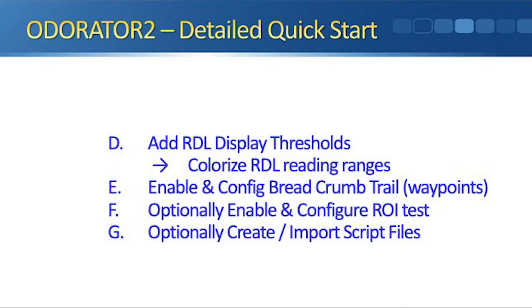After the account is initially set up, I'll typically go in and start using the software to customize the presentation and/or the instrument. Some of the options are to colorize the RDL levels. As Brian mentioned, the RDL level is required by the federal regulations. It has to be readily detectable. To make an overview of a survey more graphical, easier to understand, quicker and more efficient, the actual RDL levels can be assigned a color range. All less than 1%, of course, for a methane instrument. So it can be broken up into several ranges, and by color alone, the reading can be recognized for that range and deemed normal, okay, marginal, or problematic, all by glancing at a map and looking at the colorization of the test locations.